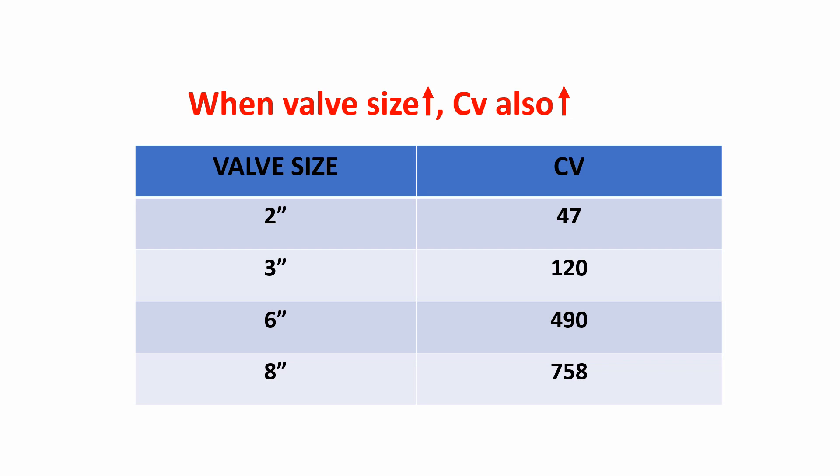You could see the three inch valve size has 120 Cv, the six inch valve size has 490 Cv, and eight inch valve size has 750 Cv. So when the valve size increases, the Cv also increases, that's directly proportional.